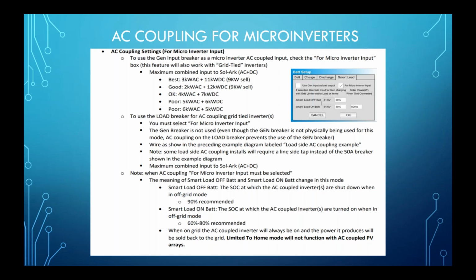The last note here, super important about AC coupling: when on grid, the AC coupled inverter will always be on and the power it produces will always be sold back to the grid. Limited to home mode will not function with AC coupled PV arrays. This is very specific, and this is in the manual. This page is straight out of the manual, so everything you see here correlates back to our manual, but it's very specific about AC coupling.